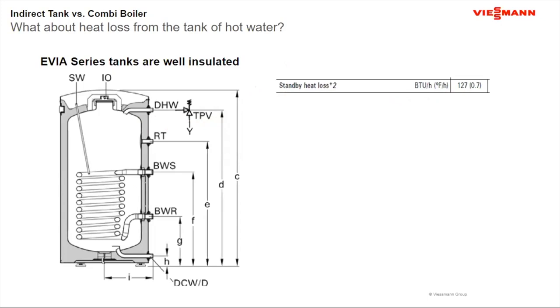So the question always comes up about the heat loss and the number of times that boiler needs to cycle if there's no demand to maintain tank temperature. If I look at that 0.7 degrees per hour, and I look at your standard control with probably a 9 to 10 degree differential from when it recovers to when it's satisfied, based on a no draw condition, just sitting there in the mechanical room of your house, your basement, the tank needs to be recovered every 13 hours. Okay, so that's not a whole lot of recovery. If nobody's using hot water, that's about twice a day it recovers.